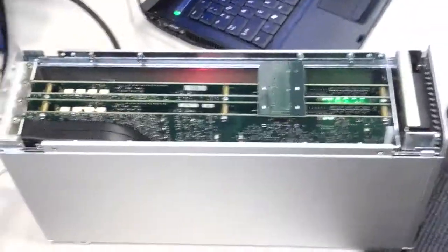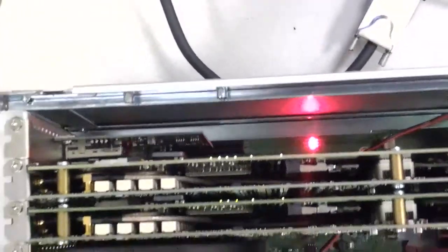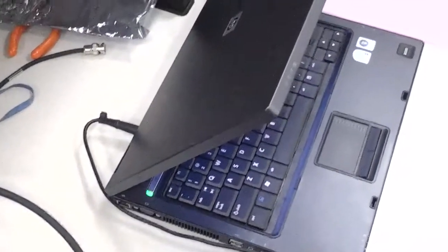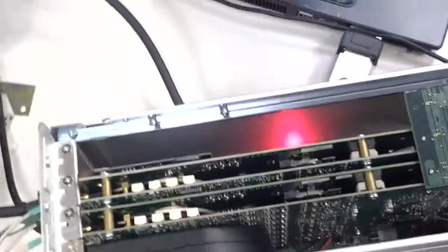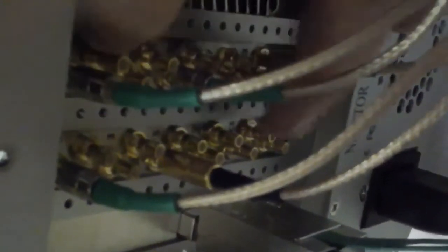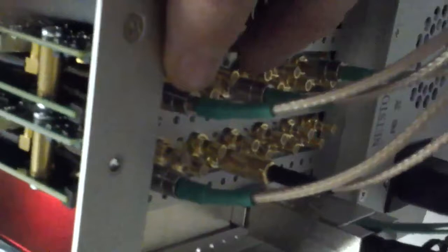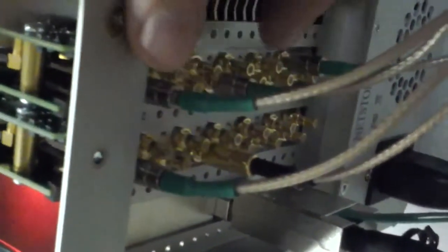Here we see a magnified view of the bus expander unit. We can see that there's a couple of PCI Express slots. In fact, those Express slots appear as if they were logically inside the host laptop, even though they aren't. Now, if I go around back of the bus expander unit, we will see the back bracket of the Octopus cards. There's 8 channels on both of the two Octopus cards, and then there's 4 auxiliary inputs at the bottom, one of which is used for the external trigger input. You can see that I've just got 2 inputs activated on each card, on channels 1 and 5 of each card.